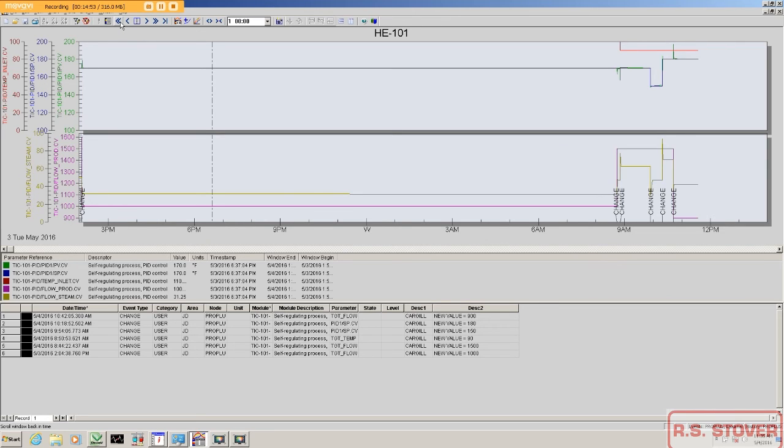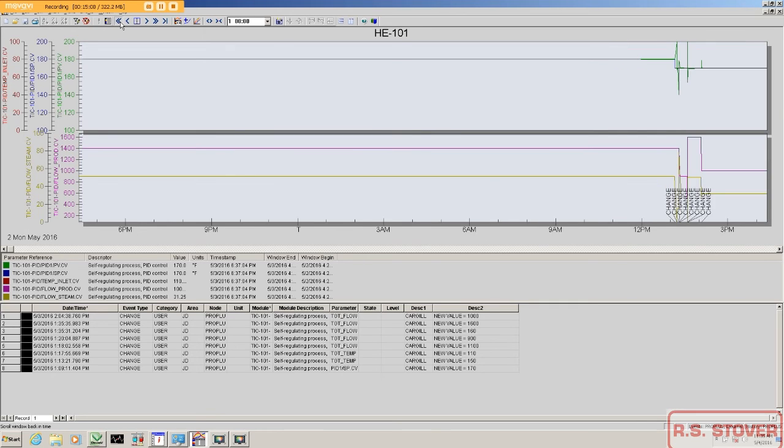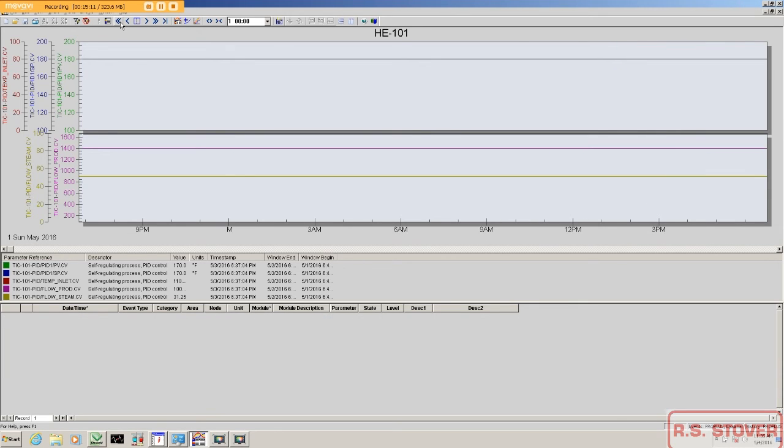So you're going to notice that as we talk about the x-axis, Process History View doesn't necessarily think in terms of set intervals. It thinks in terms of percentages. So keep that in mind as you're scrolling. As your time span increases, so does the rate at which you're scrolling. So that brings us to our next point. We have these two buttons right here: increase time span and decrease time span.